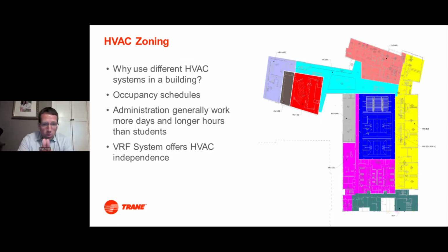HVAC zoning. Imagine an image of a high school, where in design, one of the initial things we do is go through zoning of the building. So we look at like spaces, how these spaces are being used, and when they're occupied. If you look at this top area, this orange, this is actually the main admin area of a high school. So this consists of open and closed office space, meeting rooms. This is one area that we usually always pinpoint for VRF systems.